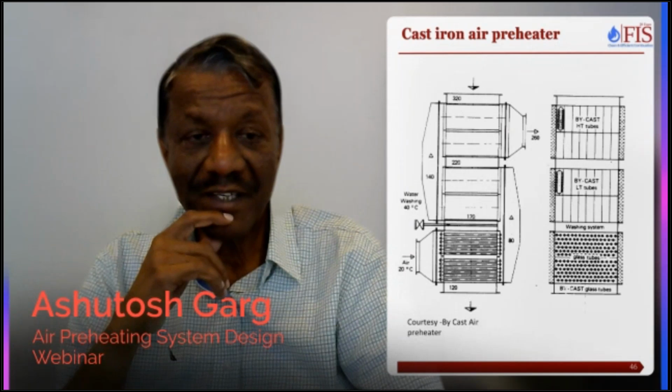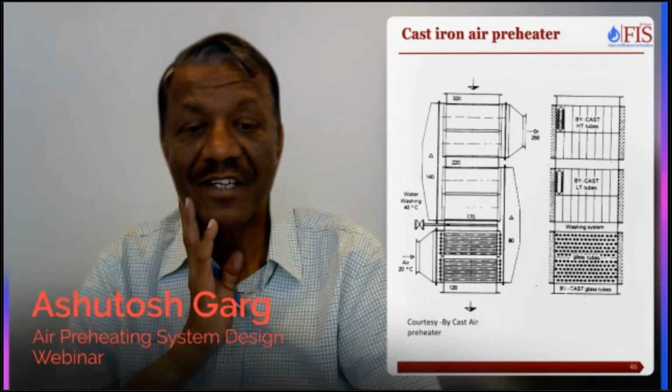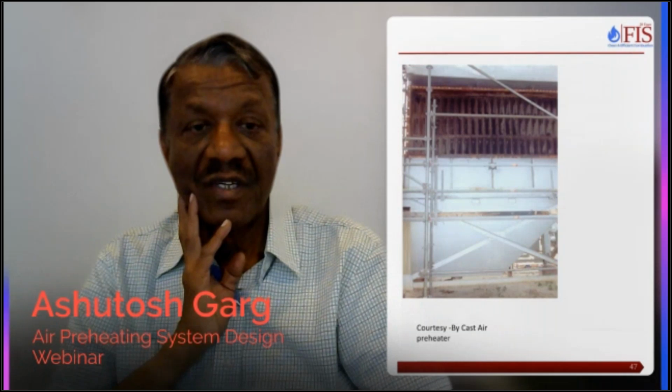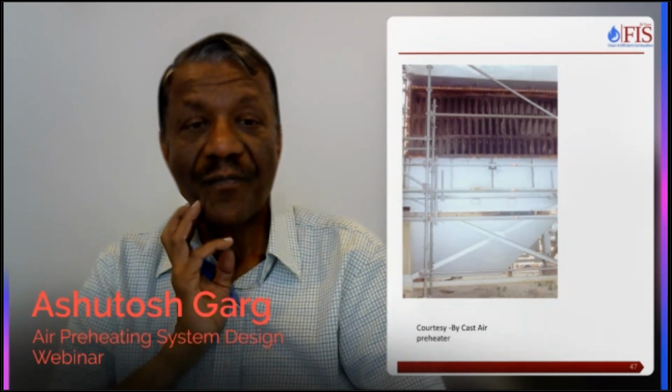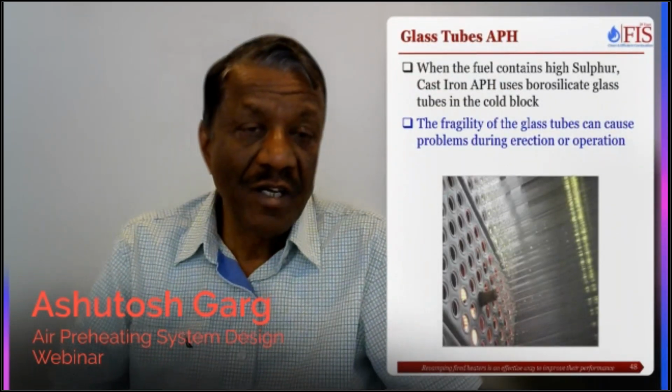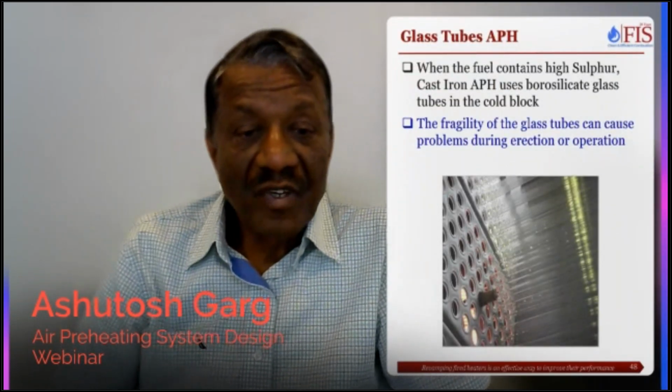Air is going through and getting preheated. Just a sketch. That's the air side. You can see that we have opened it for inspection, and you can see the air side passages. So a very effective air preheater design. These are the glass tubes.